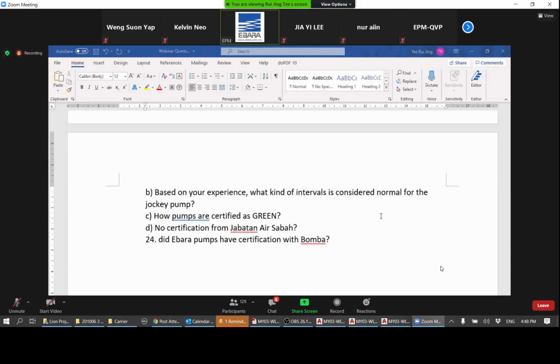ISO 9906 is basically a standard on how the pumps are tested, and MS 2616 is basically a standard on the requirements for fire pumps in terms of the selection and the duty point, and how much access it must be able to cater to and all this.